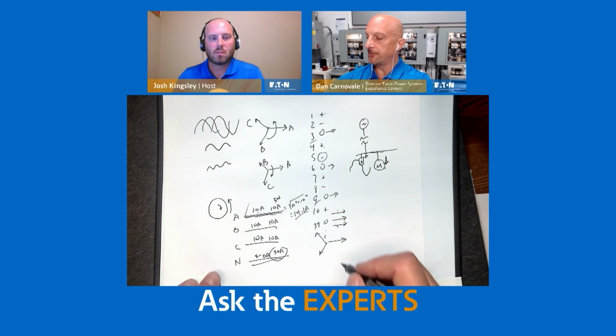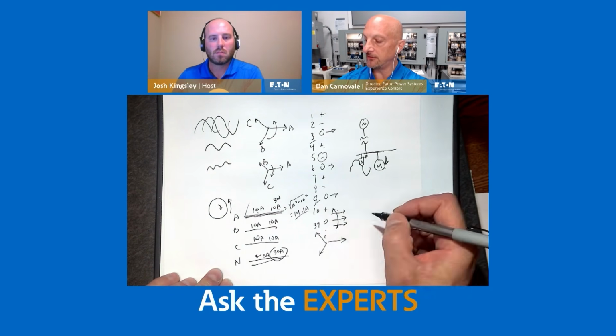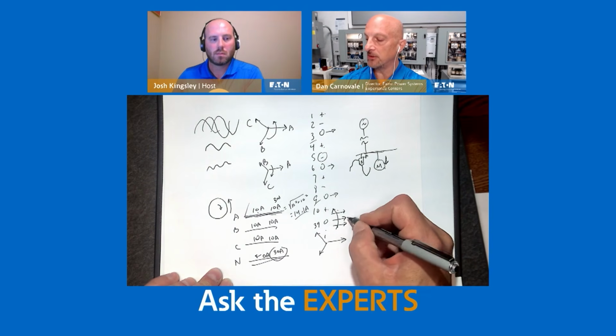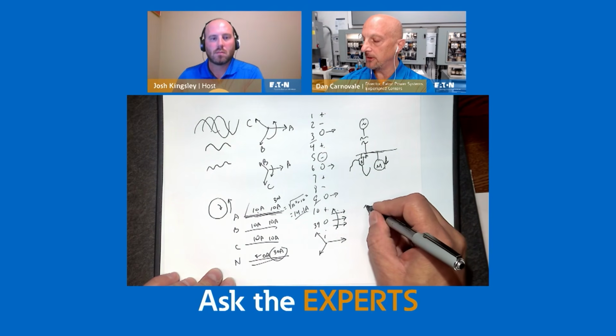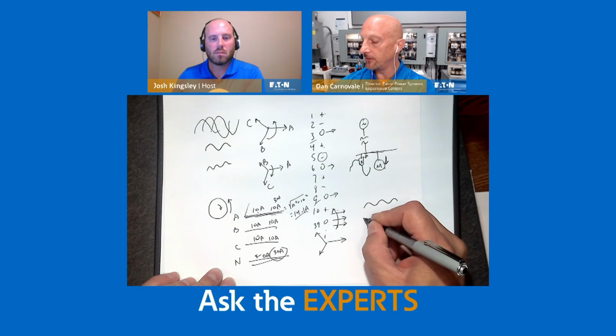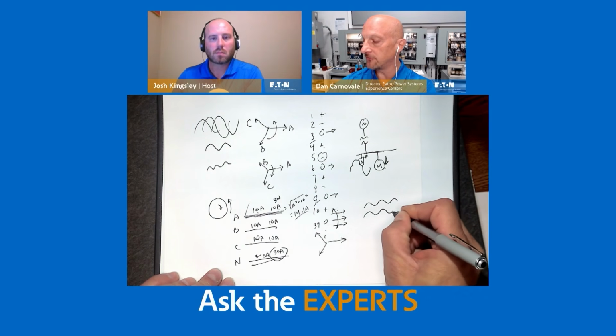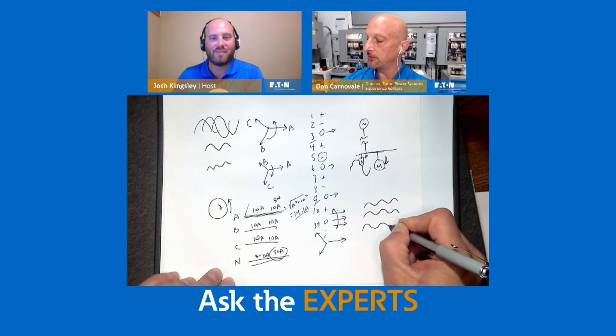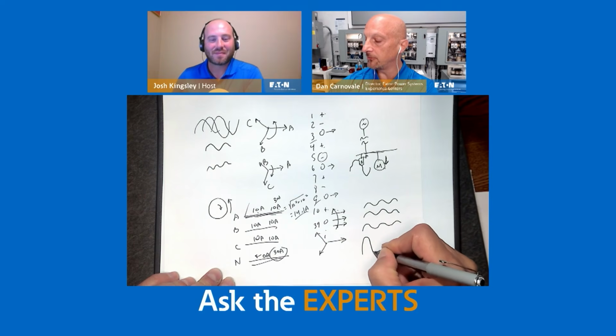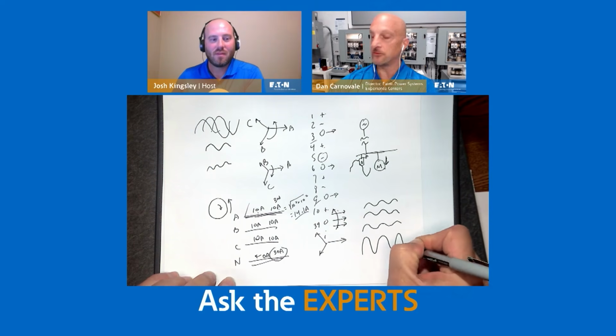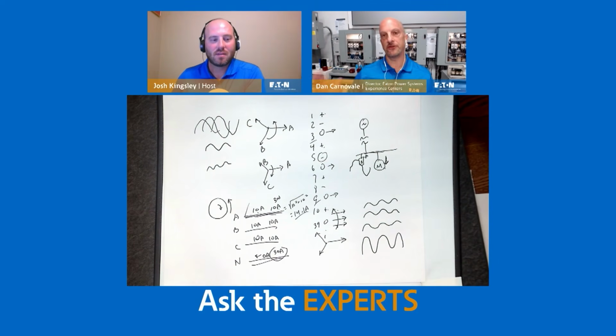And by the way, these also rotate as vectors or phasors, but they rotate together. So when you add them up on the neutral, all three of them add up exactly in phase with each other, if I could draw it correctly. And so what you end up with is 3 times the current in the neutral. So that whole discussion really goes to the fact that each of the harmonics, or characteristic harmonics, have different patterns to them.